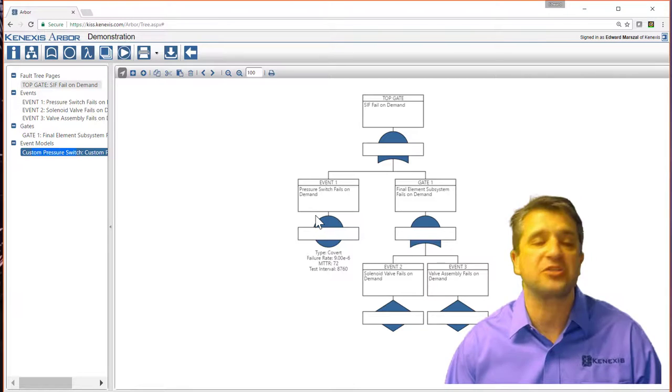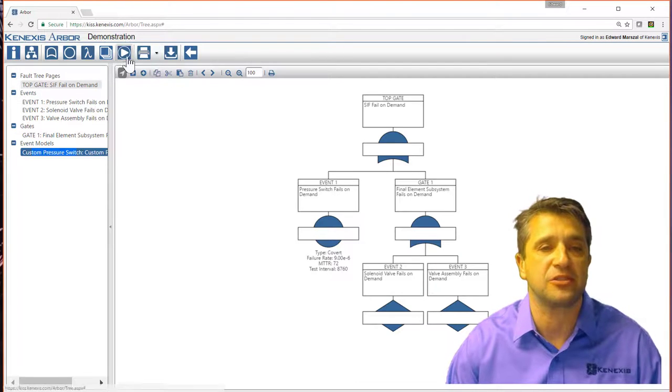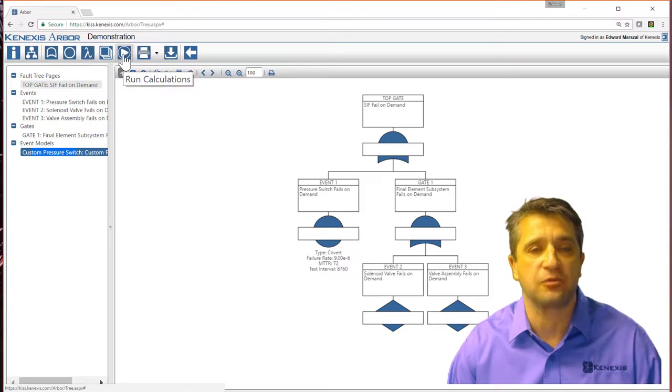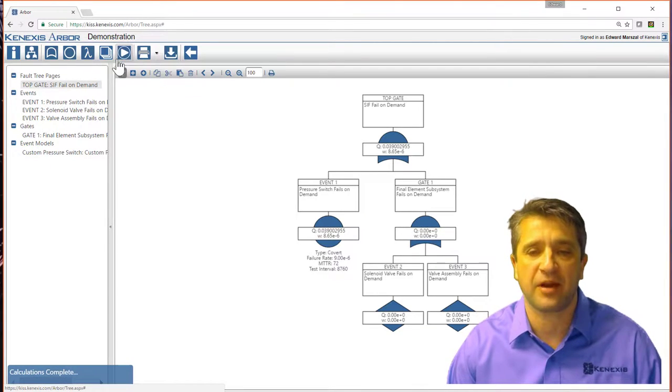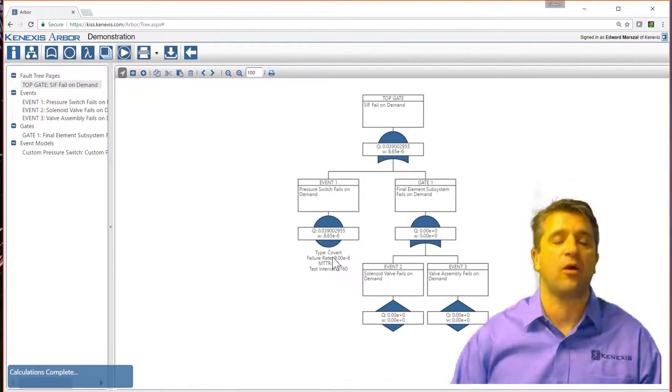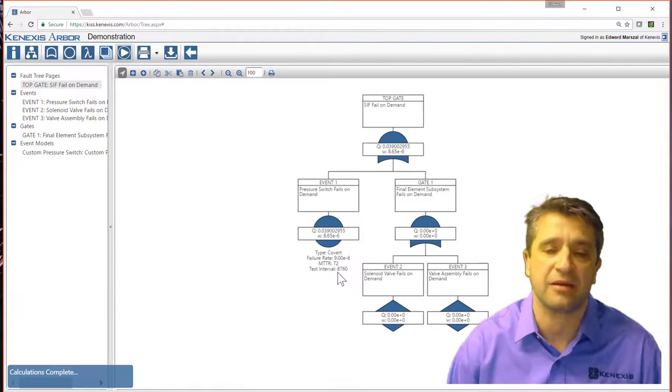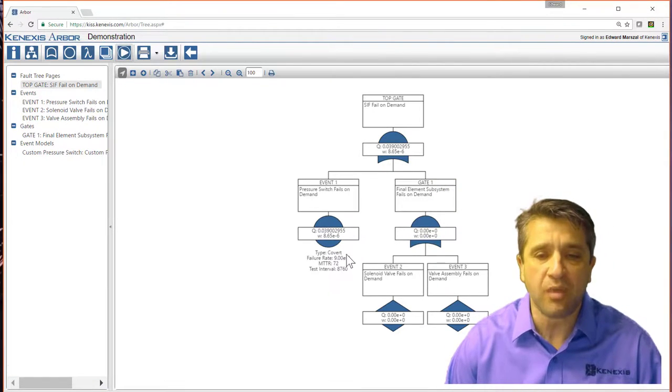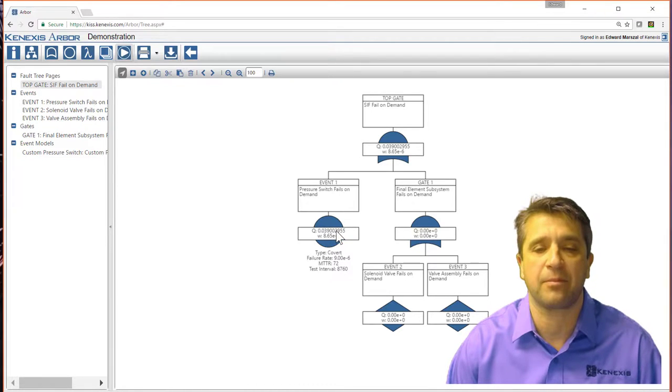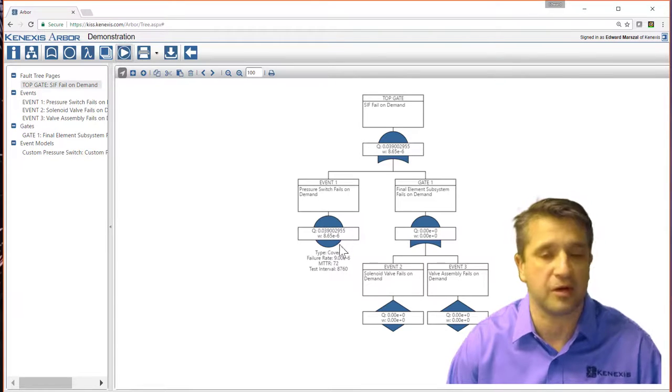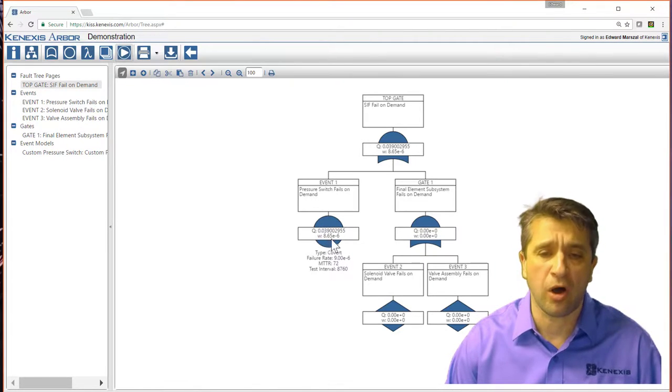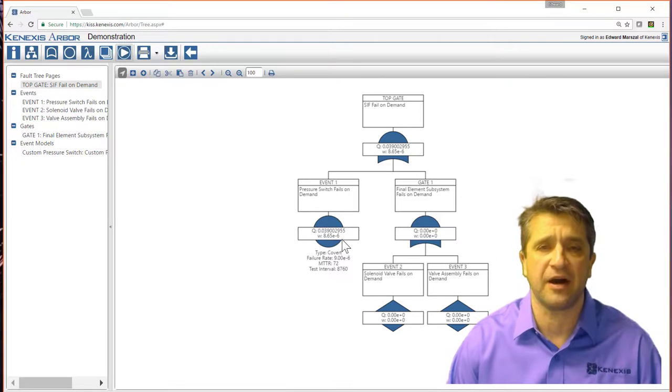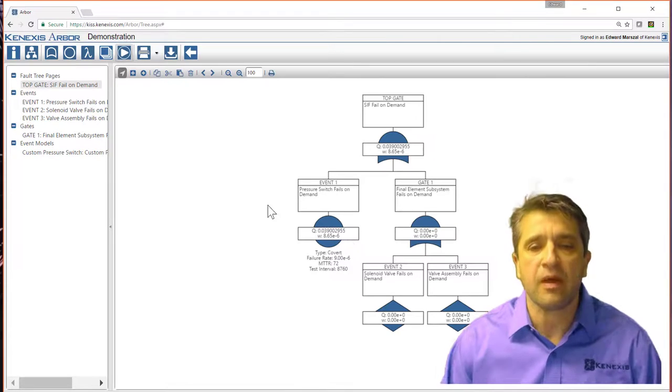I can now actually even start running calculations. So up in the action ribbon, you see the run calculations button. I press that, and it will calculate out as much as it possibly can, which is basically just the probability of failure on that pressure switch. So probability of failure is the Q, the unavailability, and also the W, which is the failure frequency.